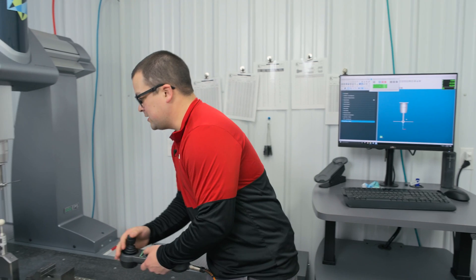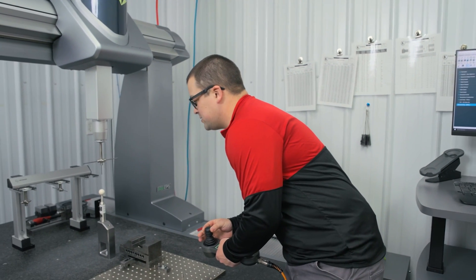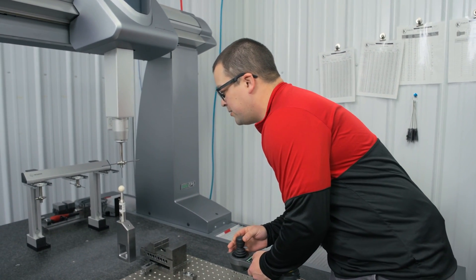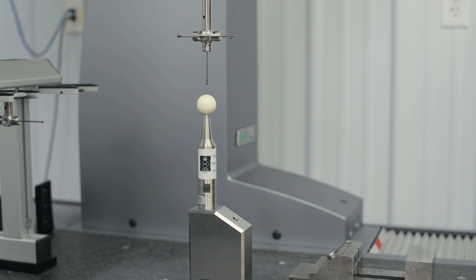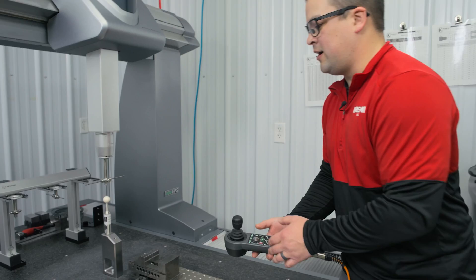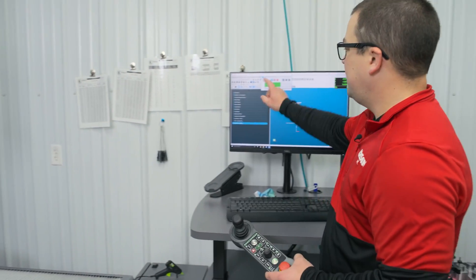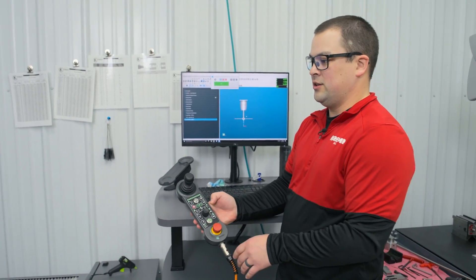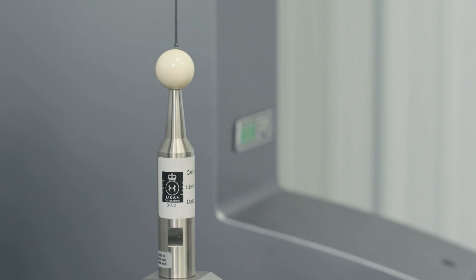So we're just going to touch the top of that sphere to let the CMM know where it's at. You don't have to hit it perfectly. Now that it knows where it's at and sphere feature will hit the green check and it's going to do its thing.